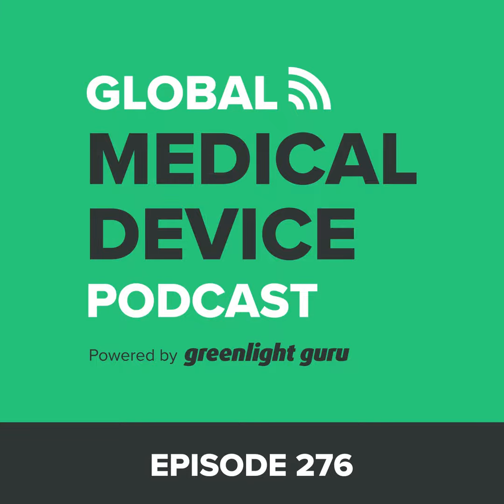So if it's a medical device, you have until May of 2024 to continue to place that legacy medical device on the market. And then a year later, May of 2025, if you have an in vitro diagnostic certificate. So there's a deadline looming ahead where if you don't comply with the new regulations, you will not be able to put products on the market. I know the European Commission and industry is a little concerned about this because there's some responses they've made, some changes in the regulations and timing and so on.